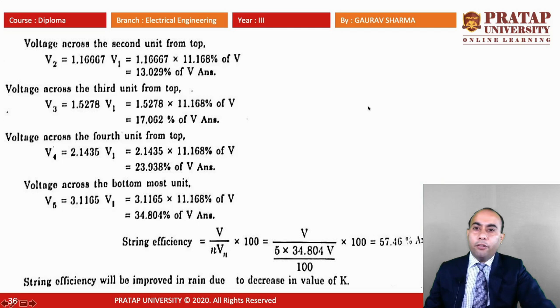So the string efficiency is V divided by n times Vn, into 100. We put the values of V and Vn, and the efficiency is 57.46 percent. Now the string efficiency will be improved in rain due to the decrease in the value of K. The value of K is decreased.